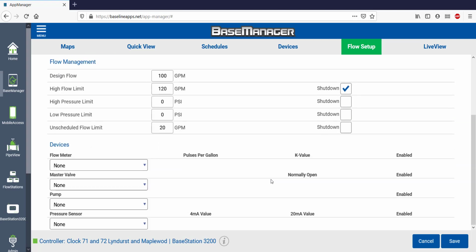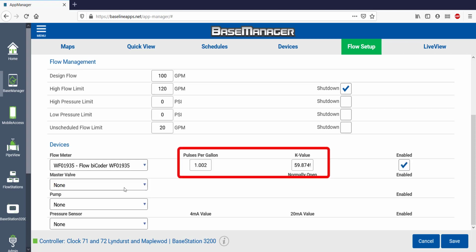The last thing to set are devices in the control point. Since I've already assigned devices under the Devices tab, I have 2 flow meters available in the dropdown. It's important that you select the correct serial number from the list that you kept during installation and don't mix up the devices. Notice that the pulses per gallon and K value automatically populate because this is a Baseline flow sensor. If it's a different flow sensor and you're using a flow biCoder, you'll need to input your own K value to get an accurate flow reading.